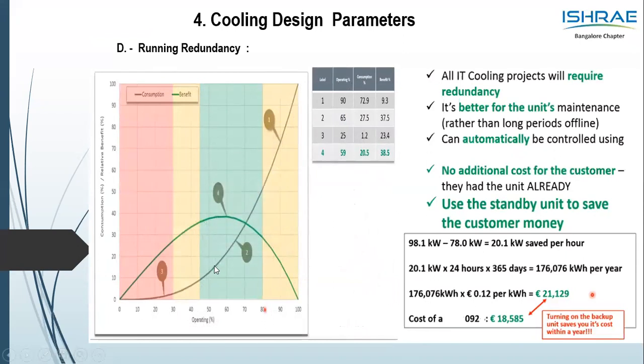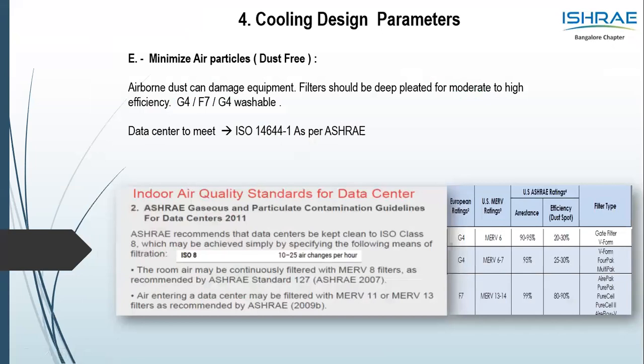So as I was telling you in the last example, by running any of the variable inverter CC units in the bracket of this blue color, 45 to 80%, you get an enormous saving. Here, if you see the serial number 4, running at 59% gives you a saving of close to 38.5% benefit. So it's very much important that we look at this. I spoke in the previous slide, and running redundancy also saves you the operational power.